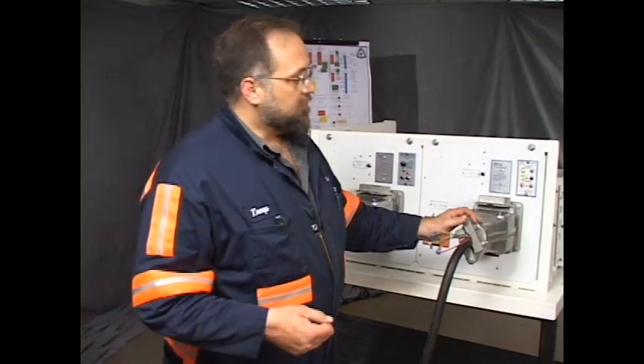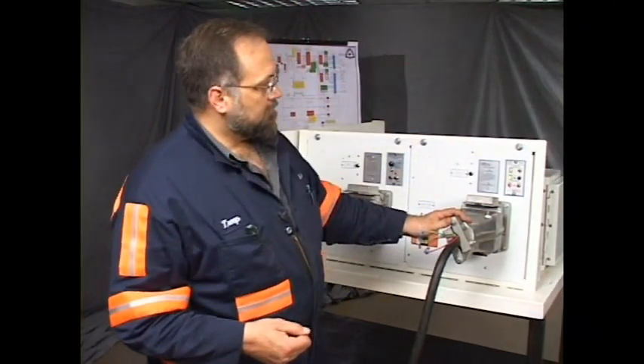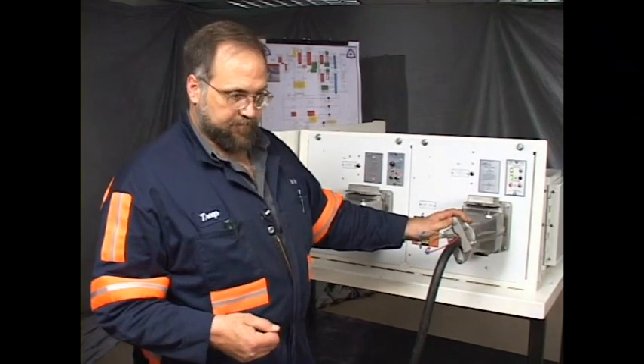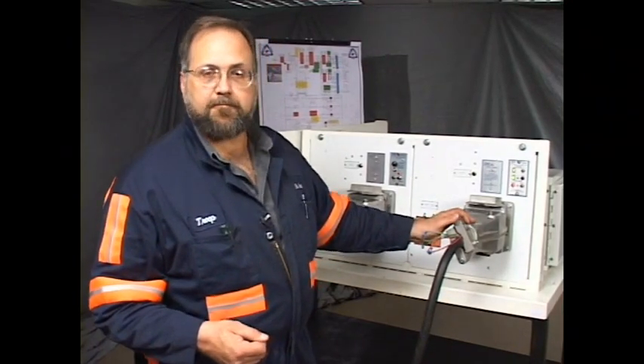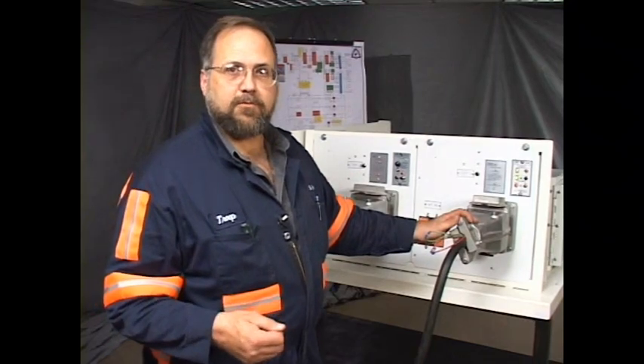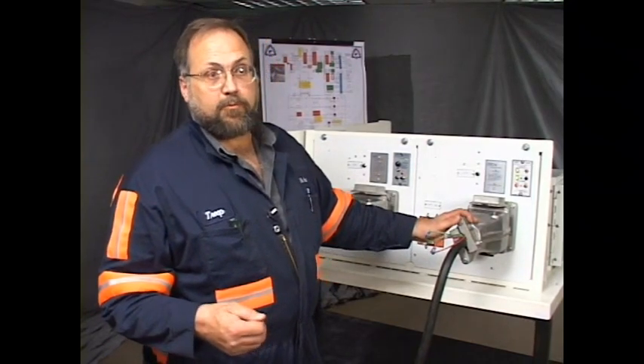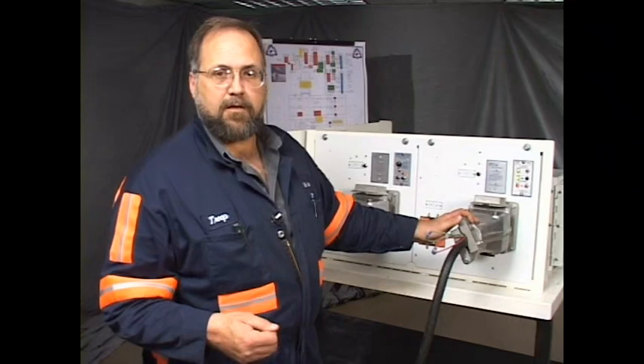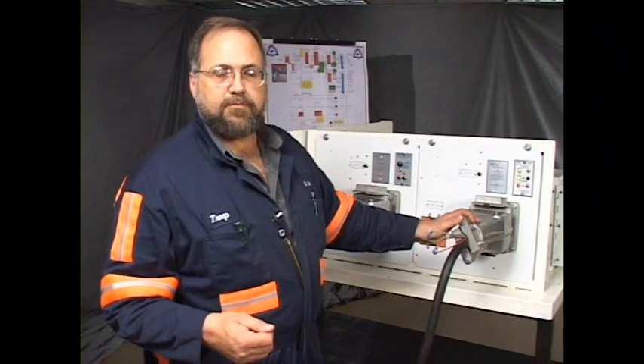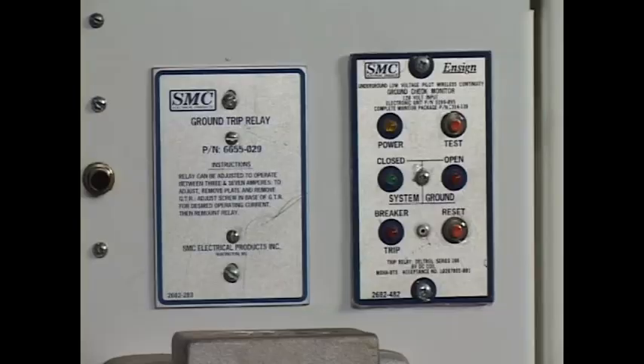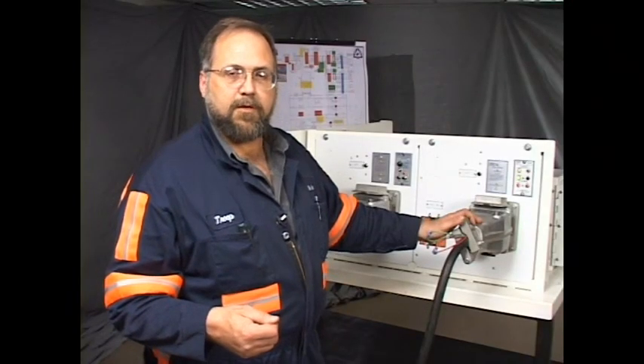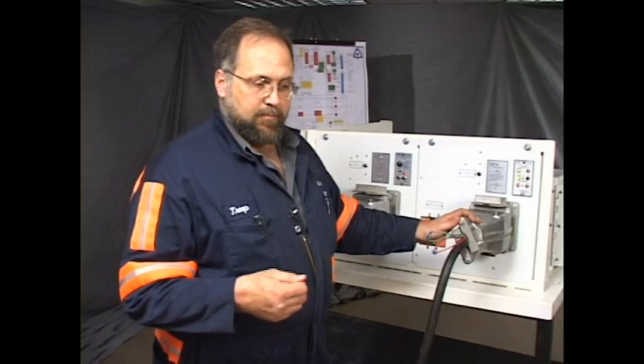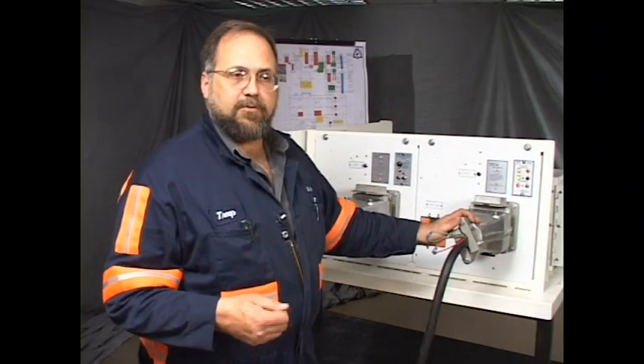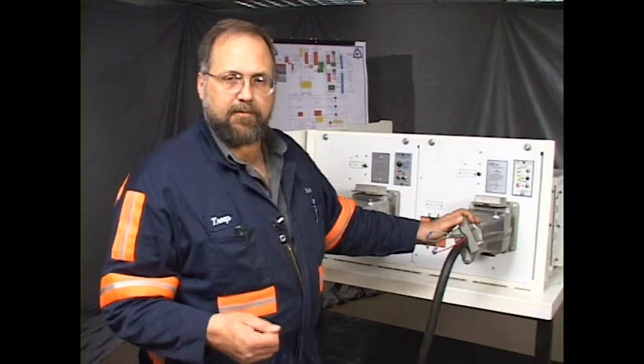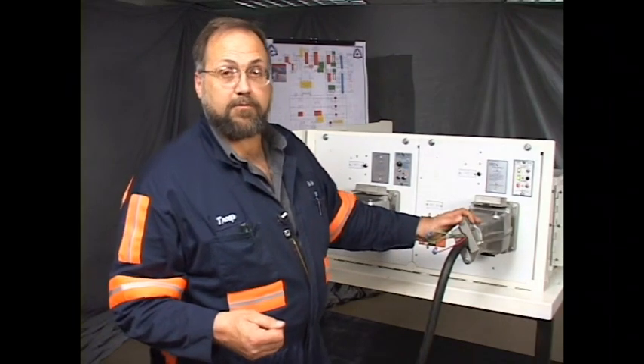The audio or tone or wireless monitor, they're called by all 3 names, employs a completely different system. It puts a high frequency signal, approximately 4,000 hertz, on the phase wires. There's a filter internal to the monitor. A transmitter puts the signal to the filter. The filter then puts the signal to the phase wires, and it's carried to the machine on the phases. Phase 1, phase 2, and phase 3, the power wires.